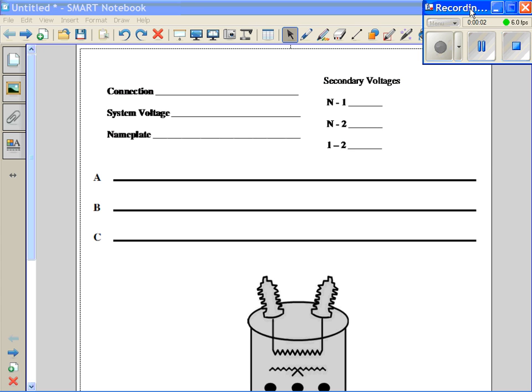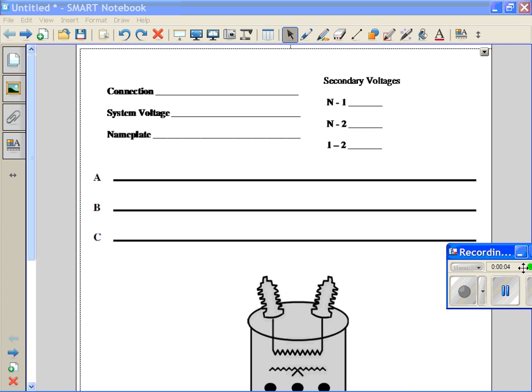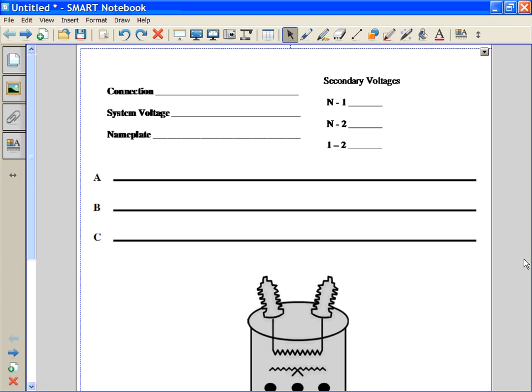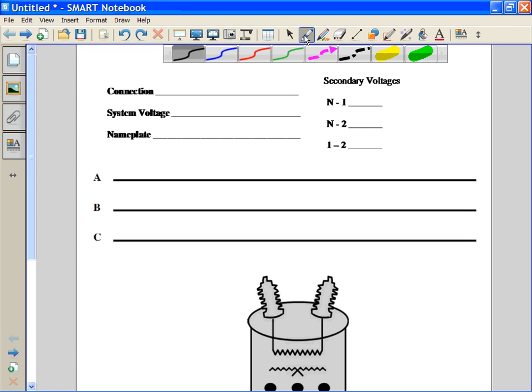The connection we're going to make here is going to be a single phase 120 volt 2-wire connection. So I'm just going to put single phase 120 volt 2-wire, and we'll make this a Y connection, and we'll just say the system voltage in this case is 7200/12470 Y.